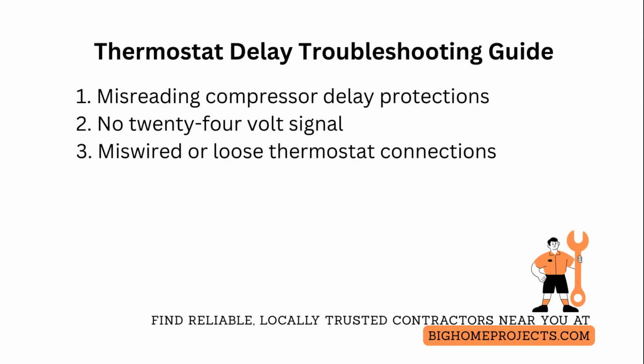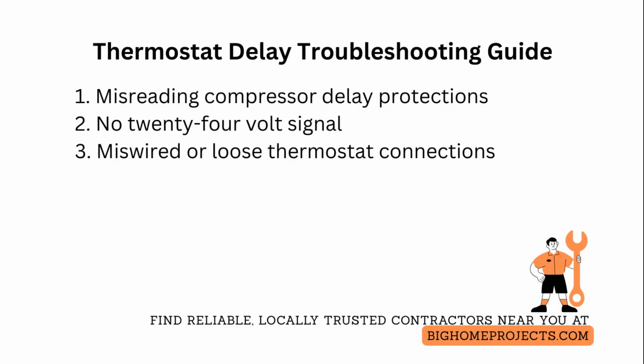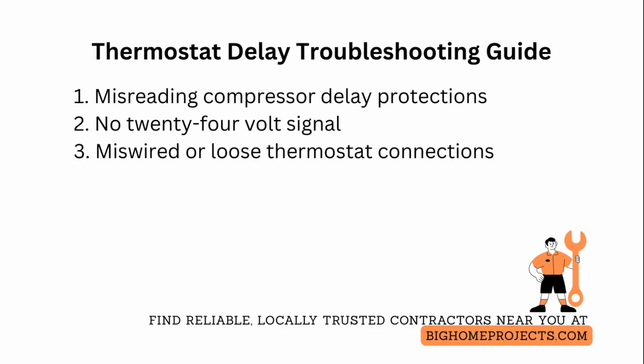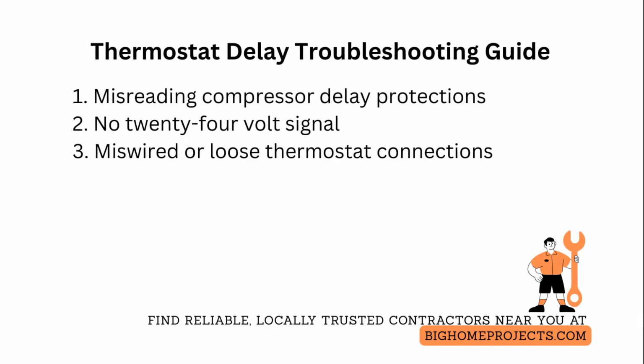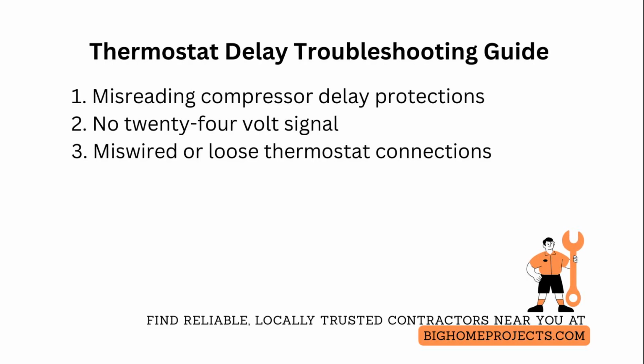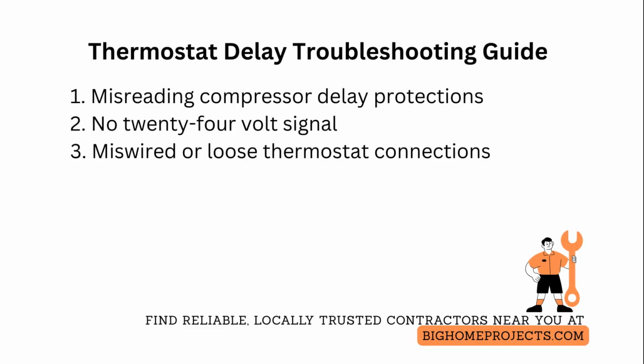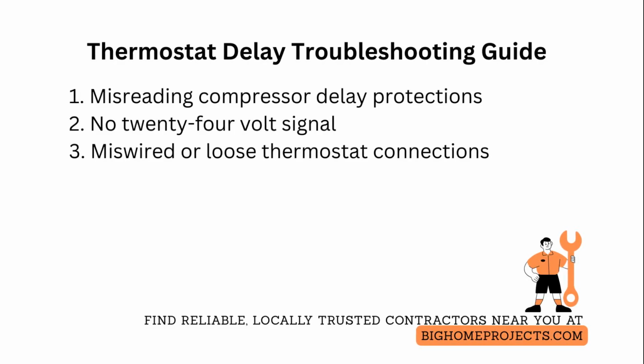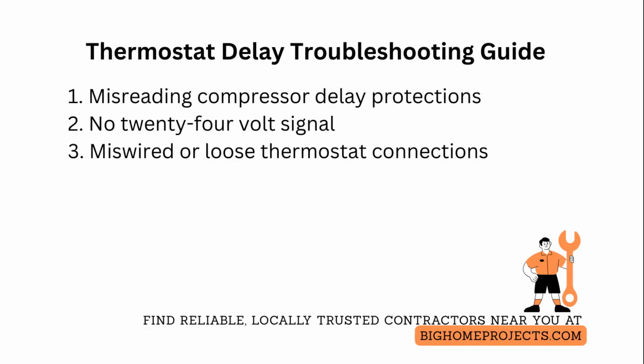One of the next frequent problems is no 24-volt signal to Y or G, often caused by a tripped transformer or blown fuse. Use keywords thermostat 24-volt test and control board fuse and remedy by testing for voltage at the transformer, replacing the fuse on the control board, or replacing the transformer if dead. The third is miswired or loose connections after replacement, searchable with thermostat wiring issues and thermostat not calling for cooling. Prevent and fix by labeling wires, photographing the original wiring, stripping properly, and verifying tight terminal screws and correct terminal mapping before powering up.